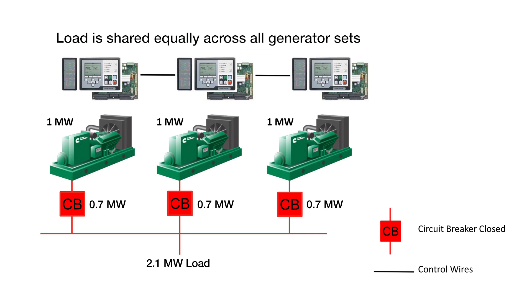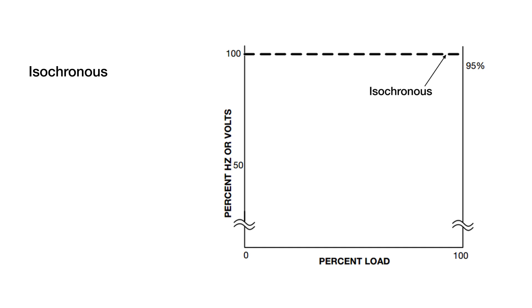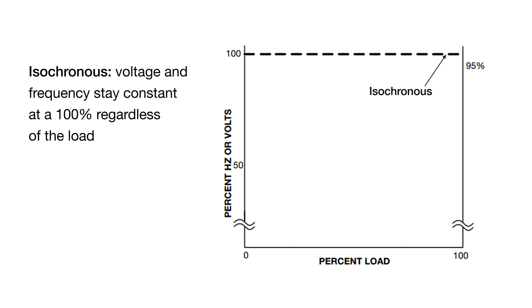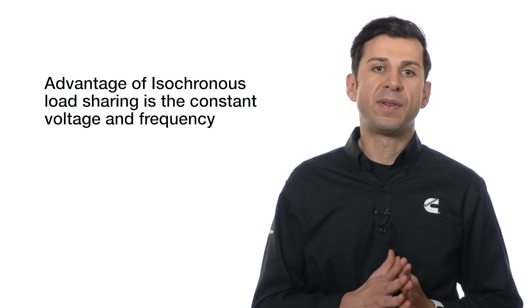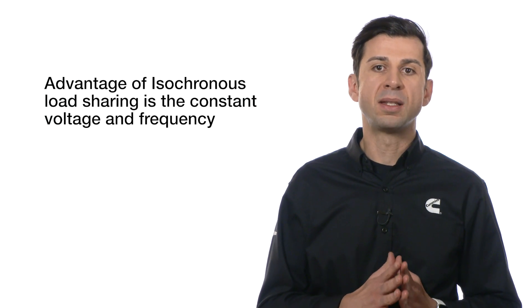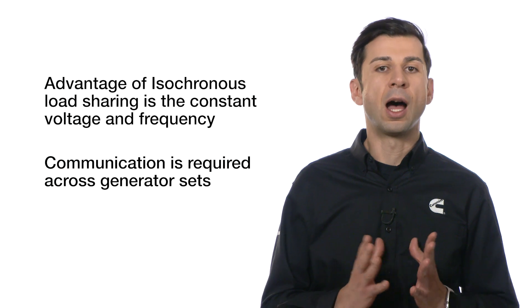Load sharing is essential to avoid overloading and stability problems on the parallel generator sets. Load sharing can either be isochronous, where voltage and frequency stay constant at 100% regardless of the load, or droop, where the voltage and frequency vary as the load varies. Obviously, the advantage of isochronous load sharing is the constant voltage and frequency.